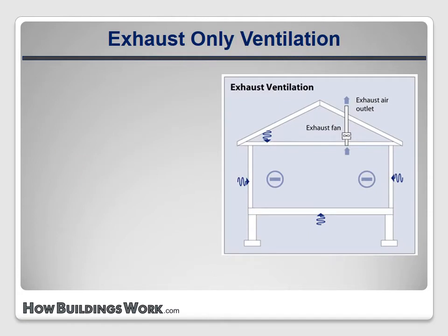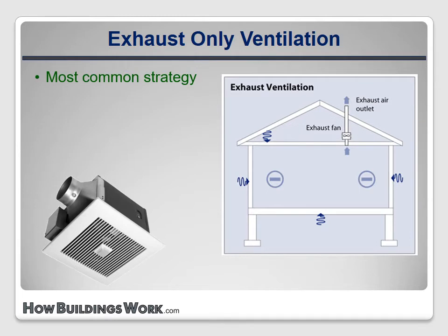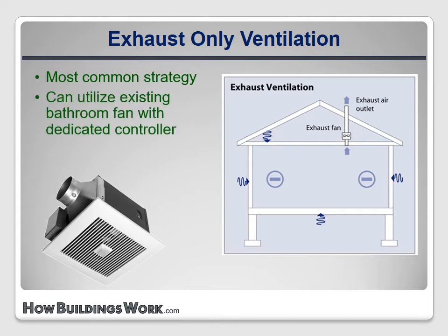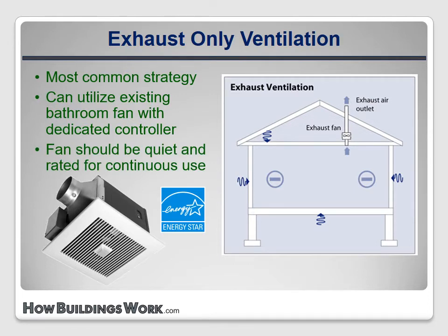Exhaust only ventilation is by far the most common strategy. As you can see from the diagram, as the fan pulls the stale air out of the house, it creates negative pressure. Wherever there are openings in the envelope, fresh outdoor air is pulled in. This strategy is usually accomplished with a bath fan, which serves as both local exhaust and whole building ventilation. In some cases, it can be done with an existing fan, but these are often not designed to run continuously. A new Energy Star labeled fan is a better choice, since it will be quieter, use less electricity, and be designed for continuous operation. These fans often have a higher flow rate than is required by the calculations, but that's good since we want them to have a high flow rate when being used as local exhaust fans to remove moisture when someone is taking a shower.